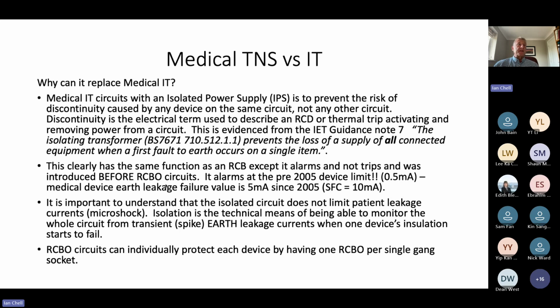So discontinuity is the electrical term used to describe an RCD or thermal trip activating and removing power from a circuit, or the same with an RCD. And it's evidenced from IET Guidance Note 7. Therefore, it clearly has the same function as an RCBO, except it alarms and does not trip. And remember, it was introduced before RCBO circuits.